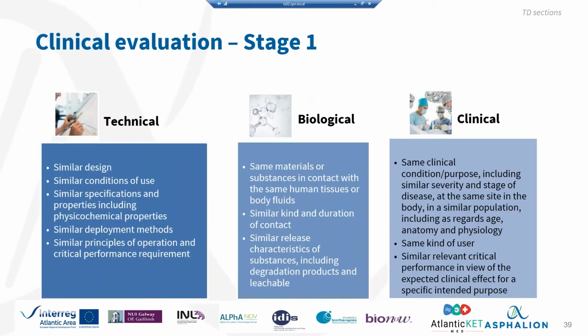So we've been talking about this equivalency. It's important to keep it in mind here. What does equivalence mean? Because when you're looking for information on similar devices, you might consider it's equivalent, but maybe it's not. Okay, so you have to keep it in mind. Equivalency means technical, biological, and clinical equivalence. It's not just that you consider that it's used for the same indication. It's got to be technically, biologically, and clinically equivalent.